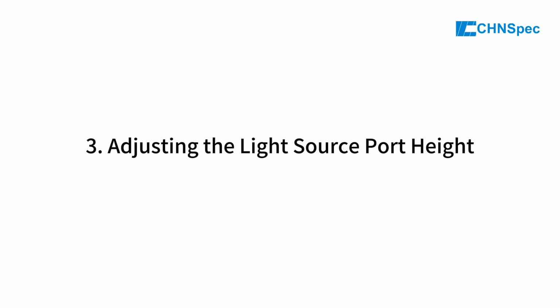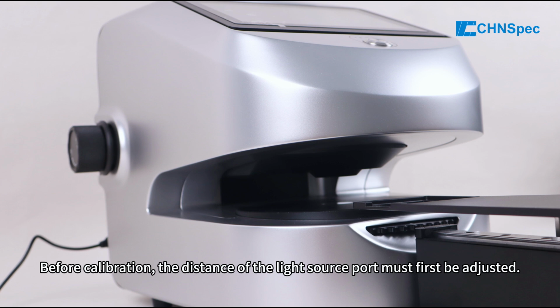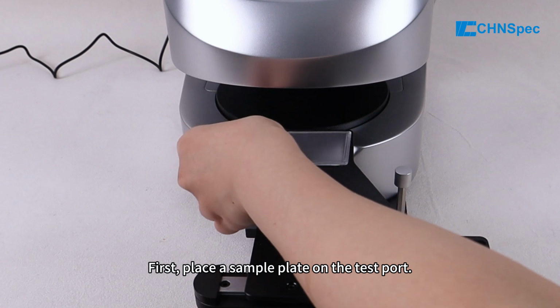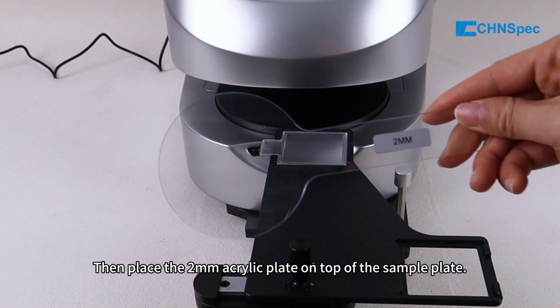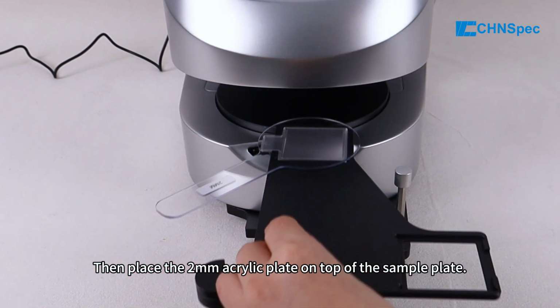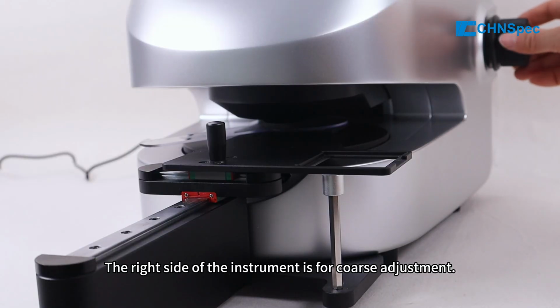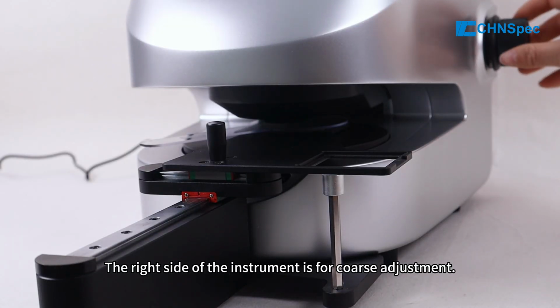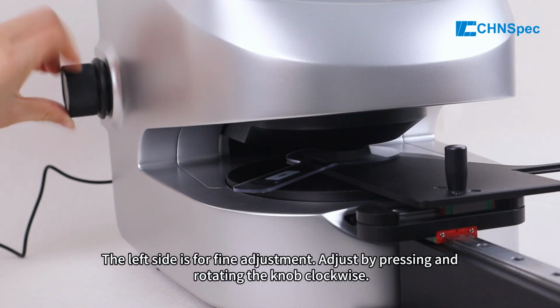3. Adjusting the light source port height. Before calibration, the distance of the light source port must first be adjusted. First, place a sample plate on the test port. Then place the 2mm acrylic plate on top of the sample plate. The right side of the instrument is for coarse adjustment. The left side is for fine adjustment.